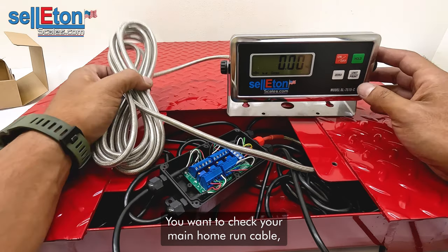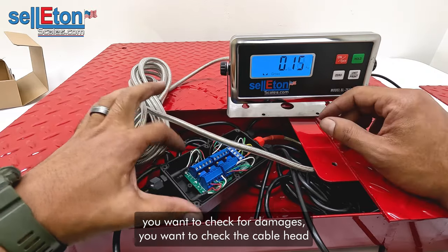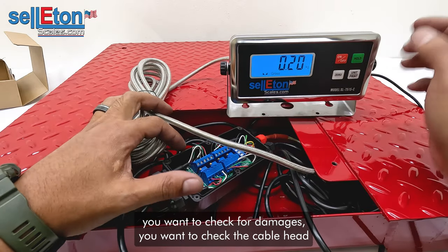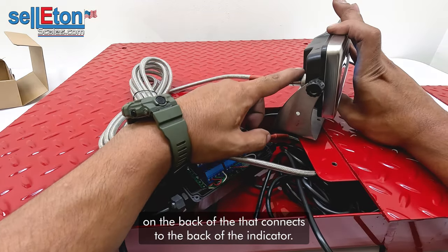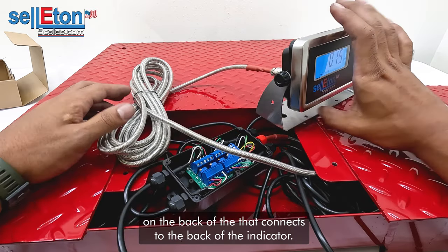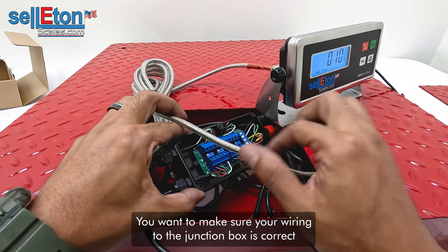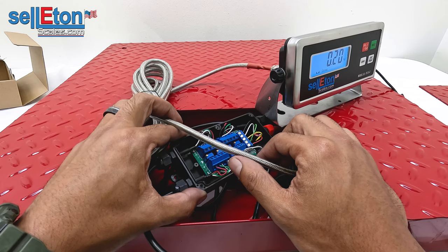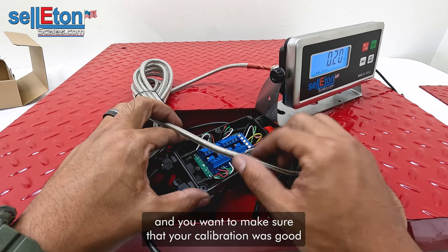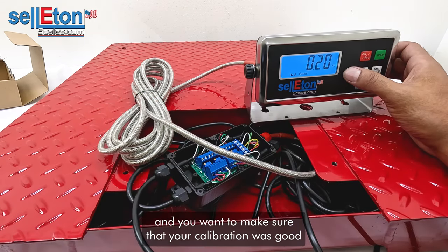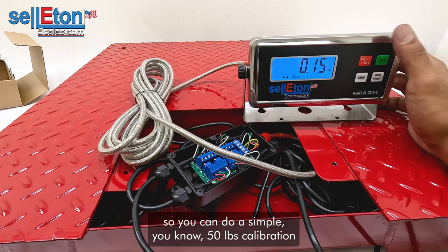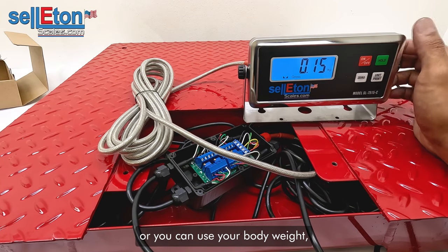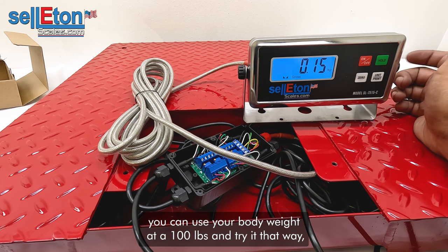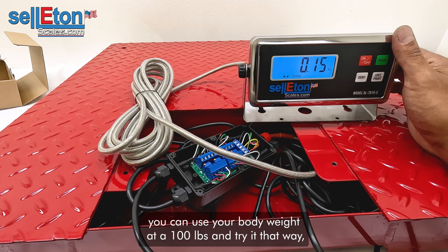You want to check your main home run cable. You want to check for damages. You want to check the cable head that connects to the back of the indicator. You want to make sure your wiring inside the junction box is correct. And you want to make sure that your calibration was good. So you can do a simple 50 pound calibration, or you can use your body weight. You can use your body weight as 100 pounds and try it that way.